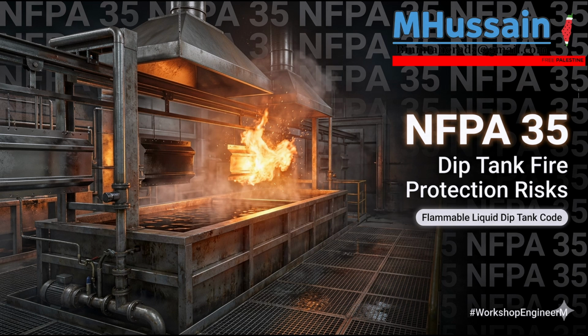Speaking of confined space entry, Section 13.2 covers what is arguably the most claustrophobic nightmare scenario in manufacturing: sending a human being inside a dark, chemical-coated tank to clean it. Confined space entry is incredibly dangerous. The standard defers heavily to OSHA regulations, specifically 29 CFR 1910.146. If a worker must enter a tank, that tank must be completely isolated from the piping system using physical metal blinds. You can't just trust a closed valve. You have to physically block the pipe.